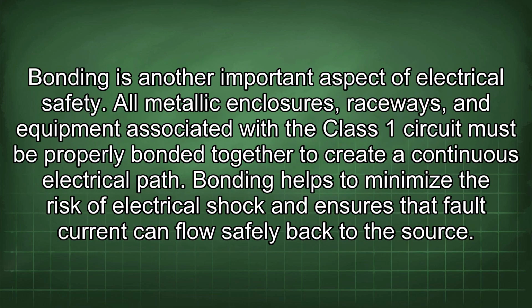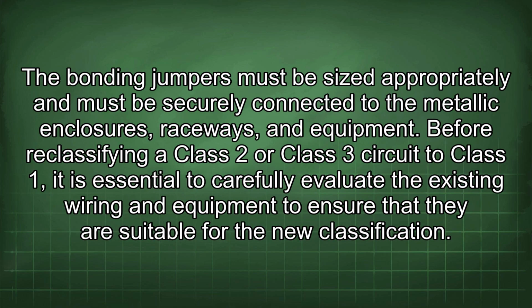Bonding is another important aspect of electrical safety. All metallic enclosures, raceways, and equipment associated with the Class 1 circuit must be properly bonded together to create a continuous electrical path. Bonding helps to minimize the risk of electrical shock and ensures that fault current can flow safely back to the source. The bonding jumpers must be sized appropriately and must be securely connected to the metallic enclosures, raceways, and equipment.